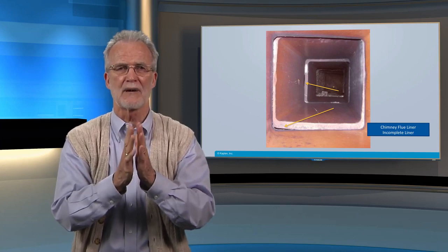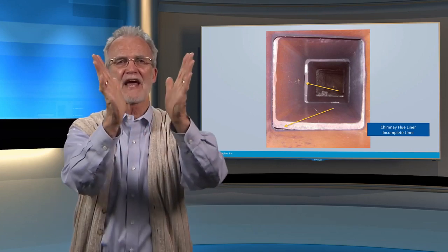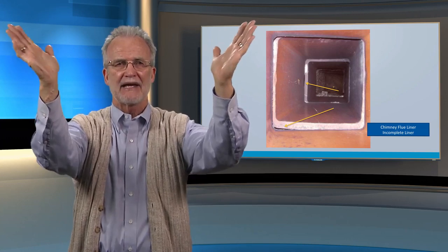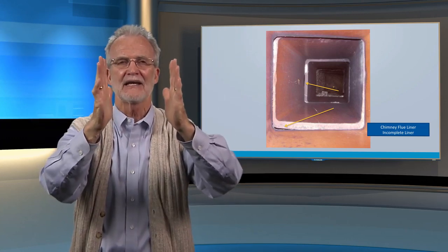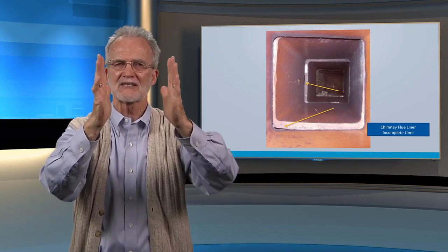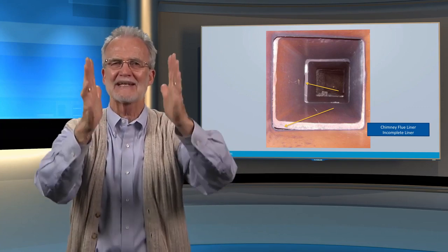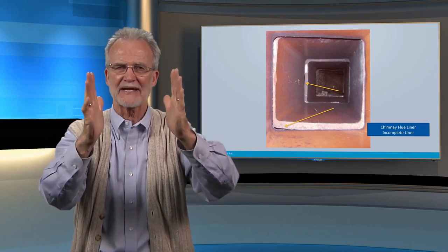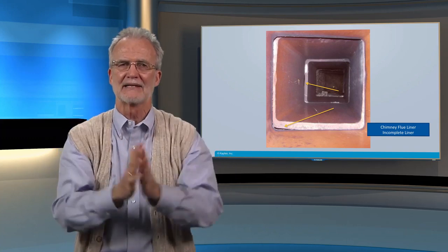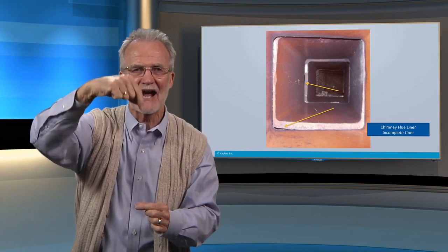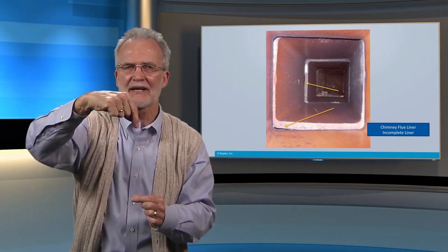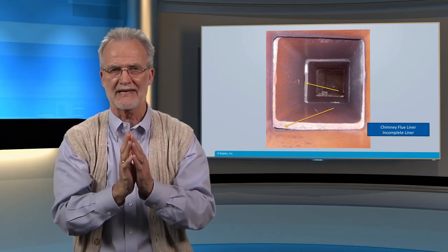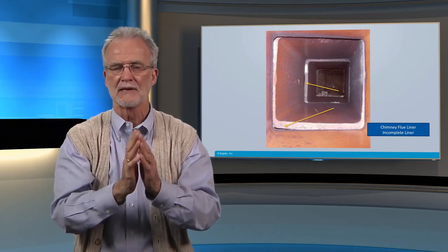Here's what you're worried about, the exhaust of that wood fireplace getting out into the chimney. It has to be contained in the flue. I'm going to say that the flue, if it's bad, is expensive. There's lots of different methods of correcting that problem, but if you can't see down that flue and see every important aspect of the lining in there, you want to put that into your report.